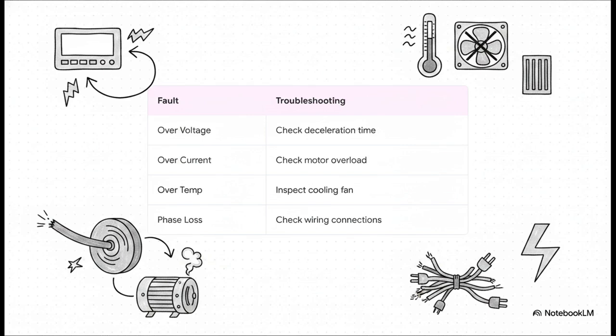You might just need to check your deceleration time. If you try to stop a massive spinning load too quickly, it physically acts as a generator and shoots power right back into the VFD. Crazy, right? An overcurrent usually points to a motor overload or short circuit. Over temperature, go inspect those vital cooling fans we mentioned earlier. And a phase loss almost always means checking your input and output wiring connections.